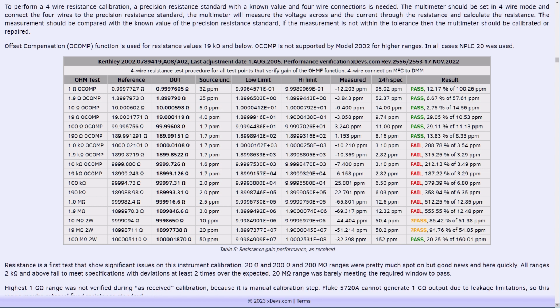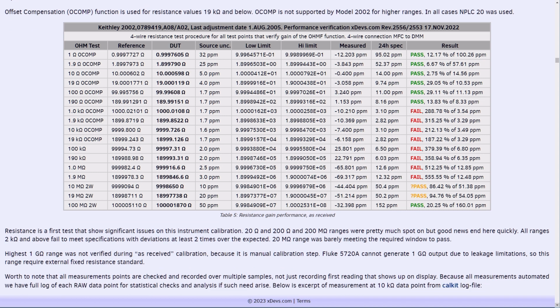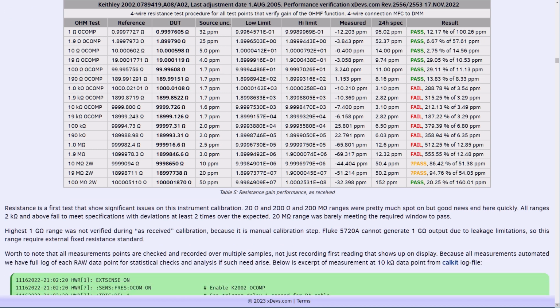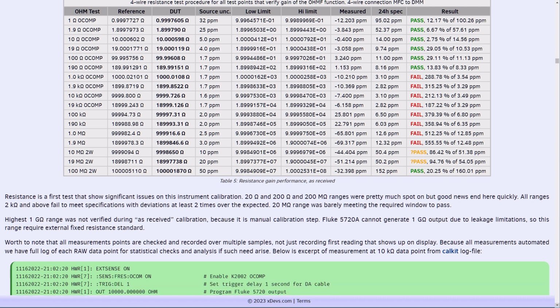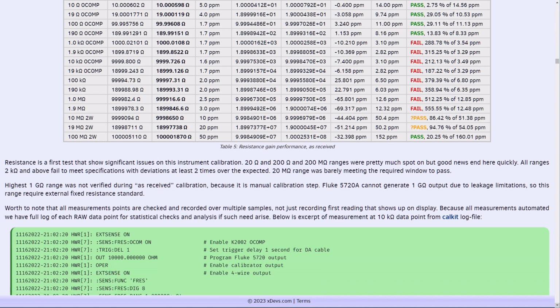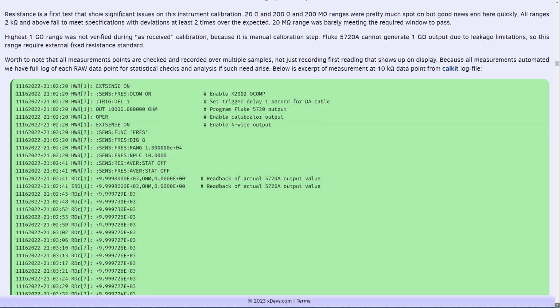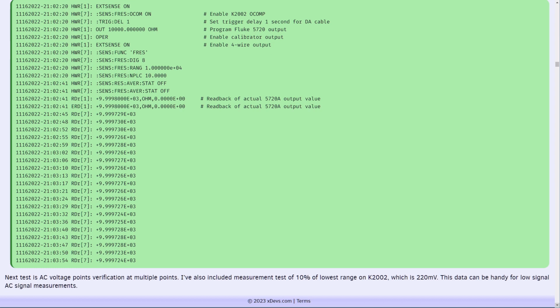And interesting to note that 100 megohm is easily passing specifications, since it's quite wide tolerance at 152 ppm. 1 gigaohm range is not tested here because it cannot be sourced directly from the 5720A calibrator. All these points were collected over multiple samples with proper settling times. Green block here lists data sent to GPIB bus between calibrator and DMM. Initial readings were discarded until stable conditions were reached.